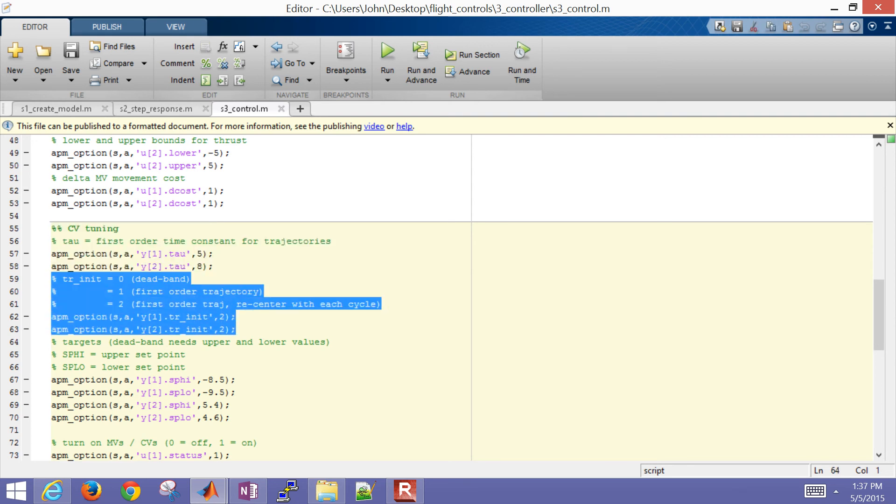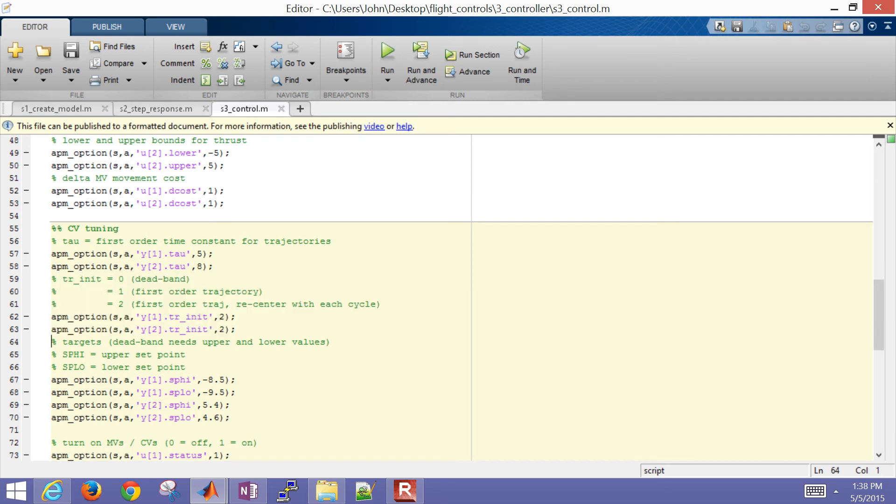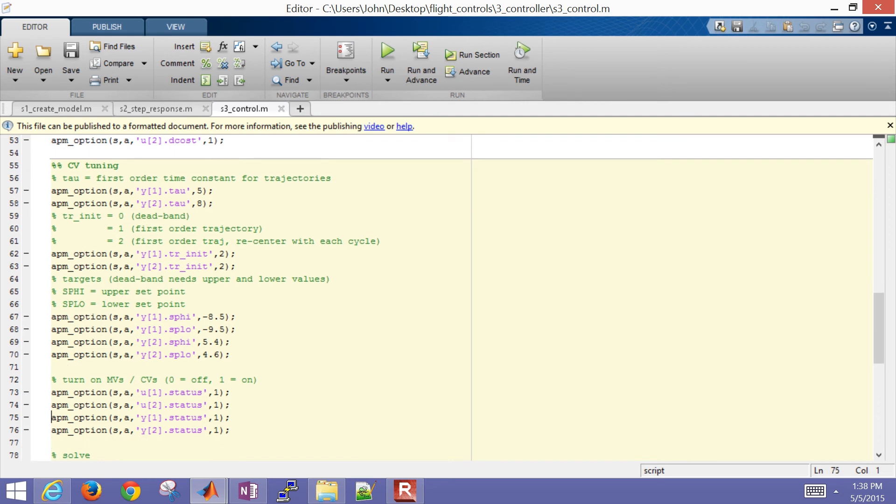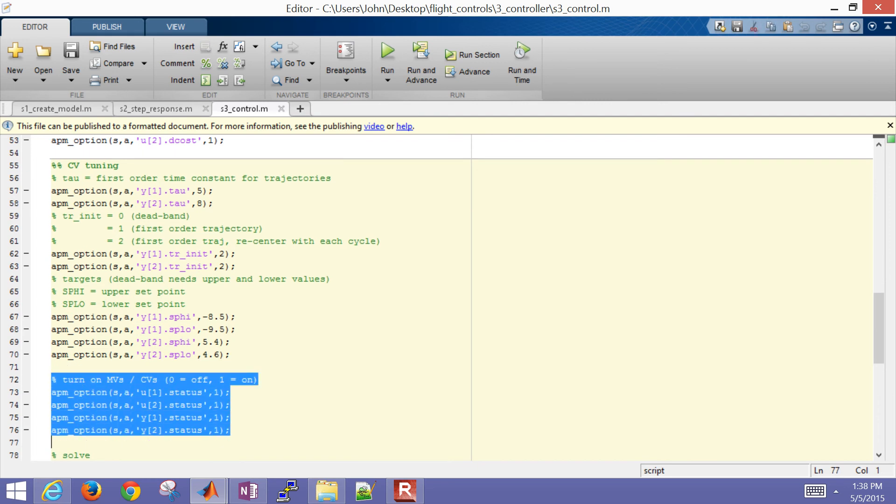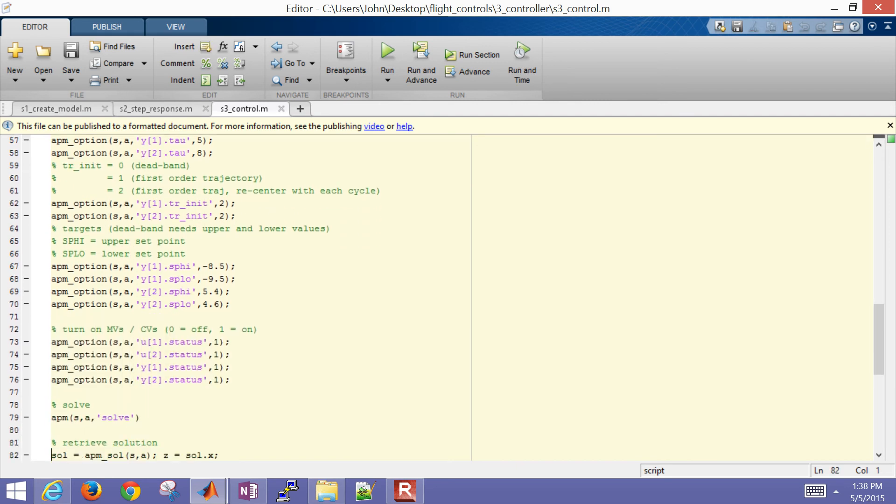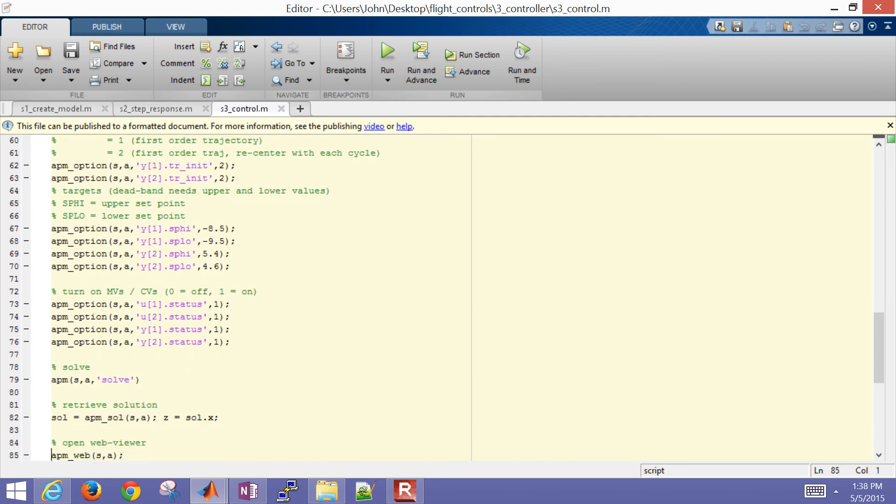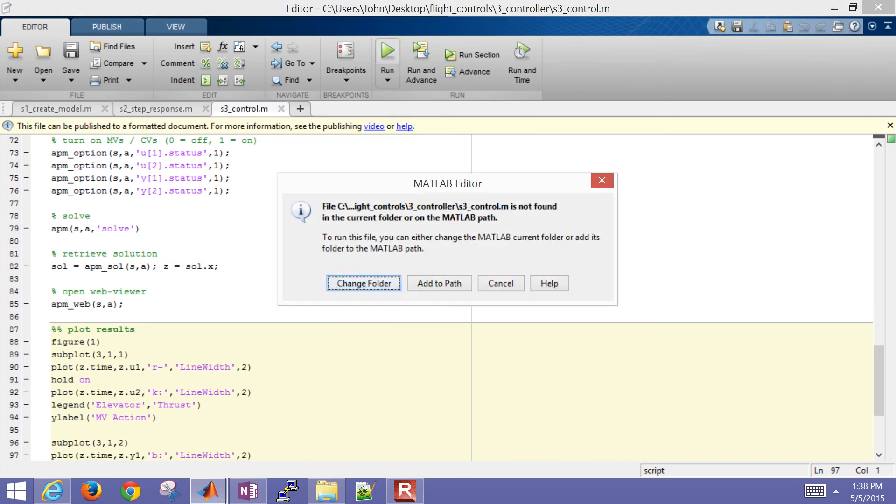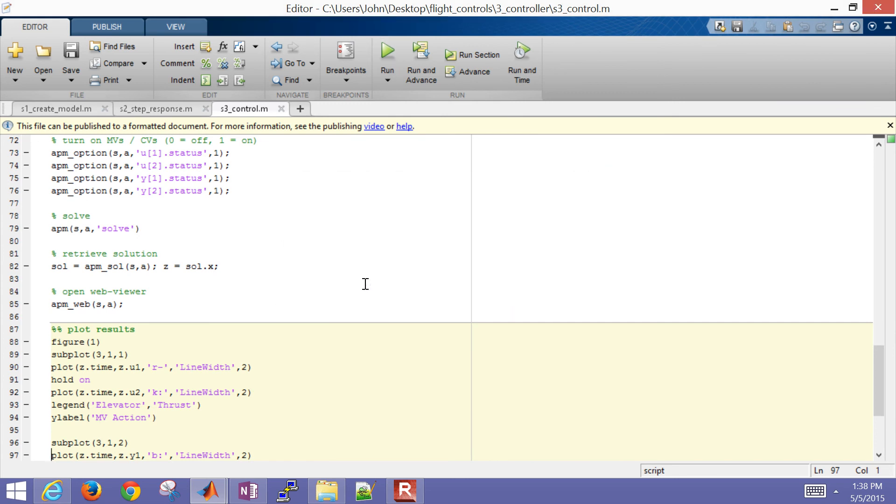Here's my initial trajectory. If you set it to zero, it's just a pure dead band. Two is going to be a first order reference trajectory that re-centers at every cycle. Here's also my set point high and low. Because I have a dead band, I have to have an upper and a lower limit for each one. Then I turn on my MVs and CVs and go ahead and solve my problem. The rest of it is just retrieving the solution and looking at the results. When I run this, it's going to run the controller.